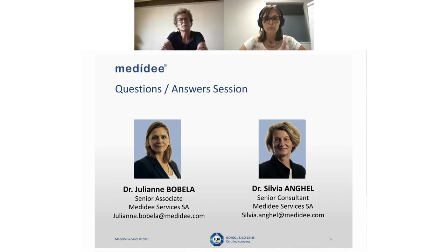And what about multicentric studies? How are we managing that? For multicentric studies, this is a bit different for IVD medical devices, where you don't need to list as part of your study plan what sites are actually going to participate, but you need to have a list ready, where you cite all the different study sites which have participated in your clinical performance study.